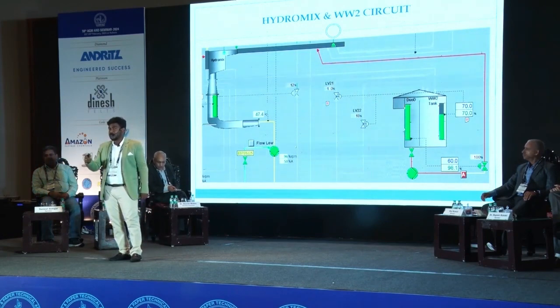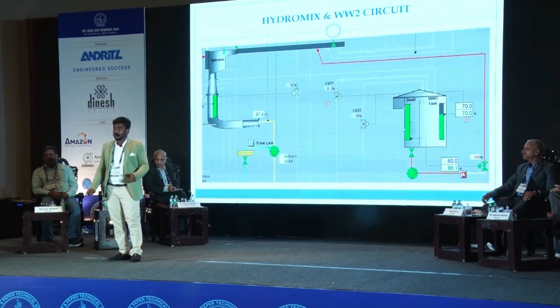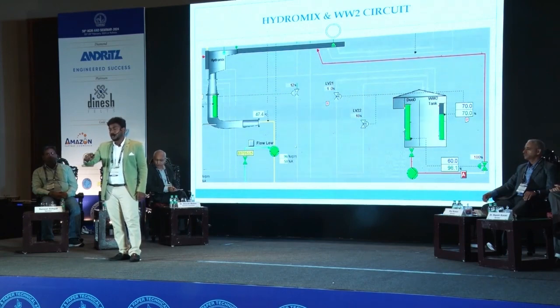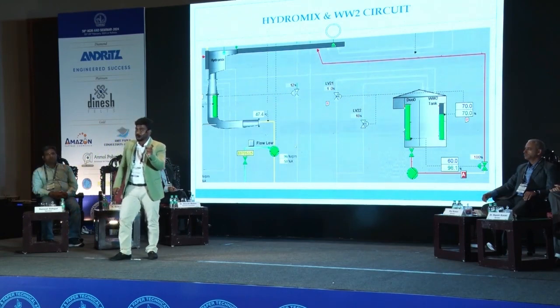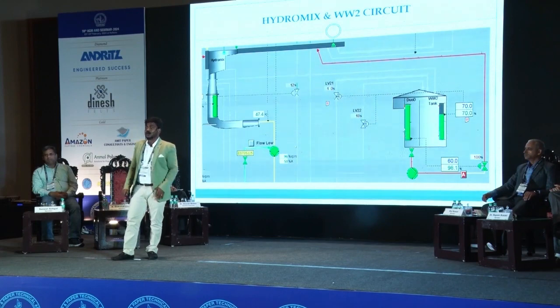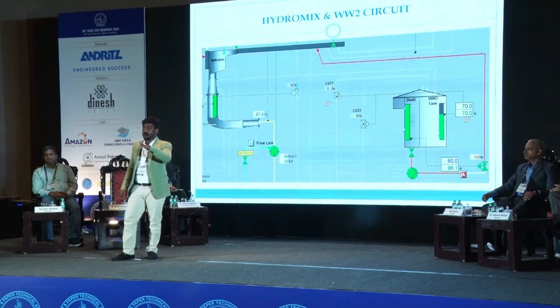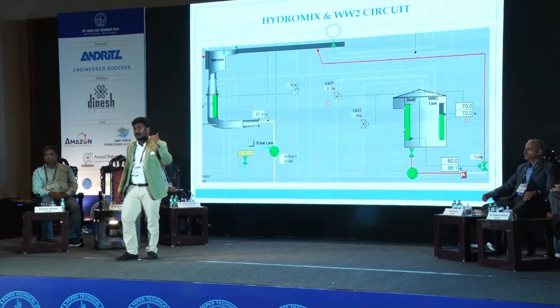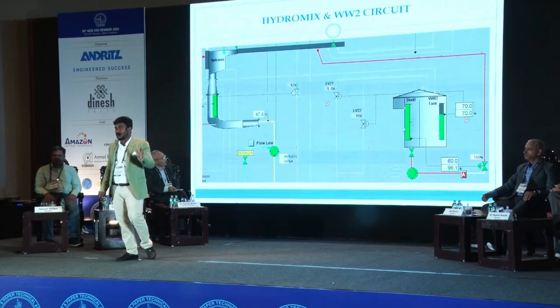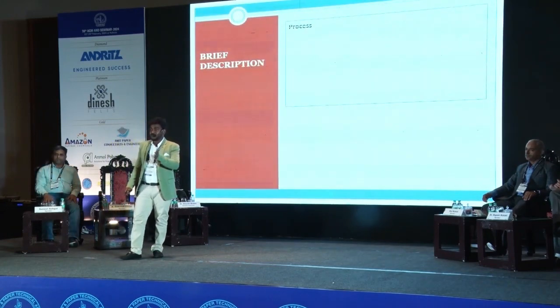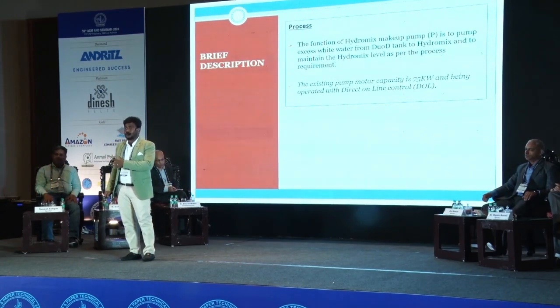This pump is equipped with DOL, a direct online starter, and it runs continuously at full speed, 100% speed. The level to the hydromix is controlled by the control valve, which is always operating at only 30 to 45% opening. So there is obstruction in the valve, which is restricting the flow, whereas the pump is running at full speed at all times, 100%. So what we proposed is to introduce a variable frequency drive instead of this DOL.